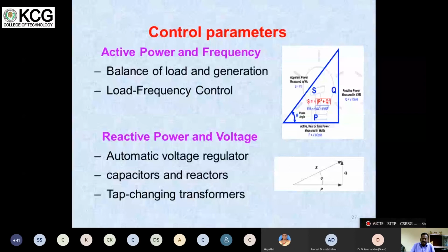And reactive power. Reactive power controls the voltage. If the reactive power supplied from the generator is more, then voltage is more. If it is less, then voltage will be lesser. How is it controlled? Voltage control is done by the automatic voltage regulator, that is, the excitation system of the generator. Any generator will have an excitation system. The purpose of the excitation system is to generate the voltage, to induce the EMF in the stator, to keep the generator terminal voltage constant, and to keep the reactive power demand in the grid within the limits. So the automatic voltage regulator plays a major role in controlling the voltage and supplying the reactive power in the grid.